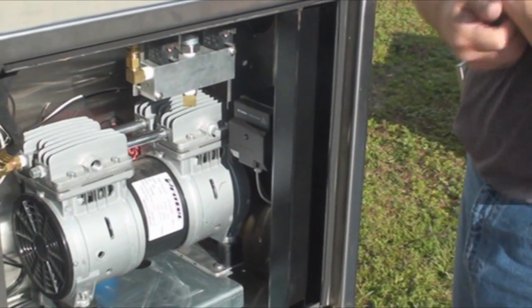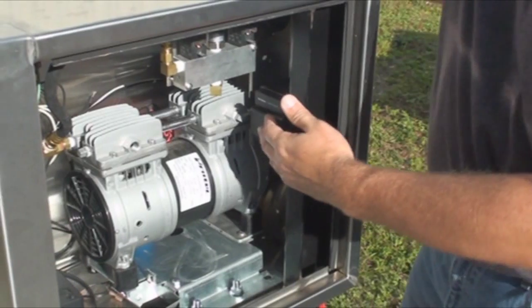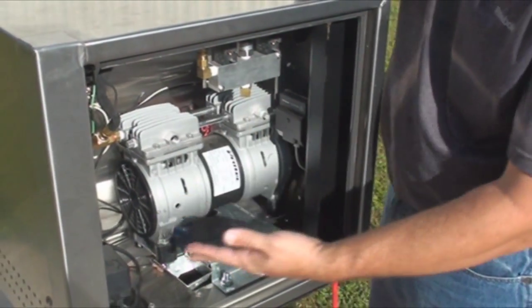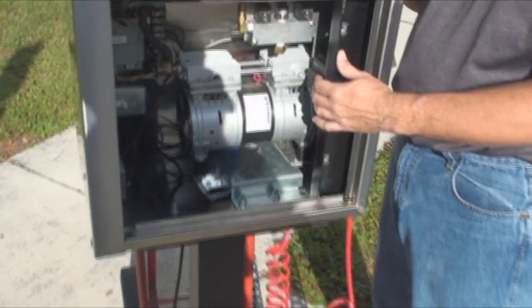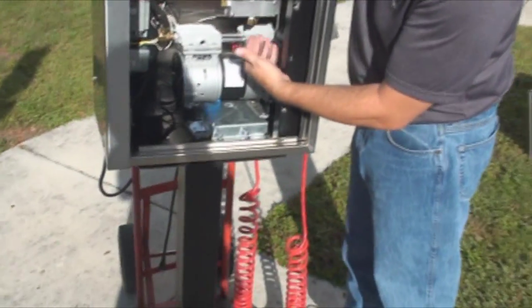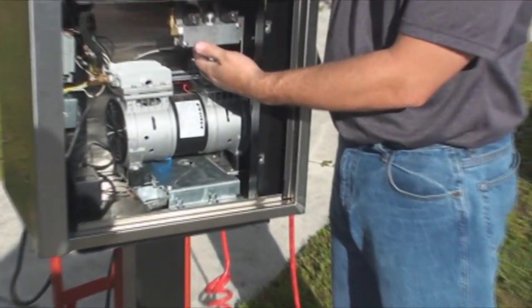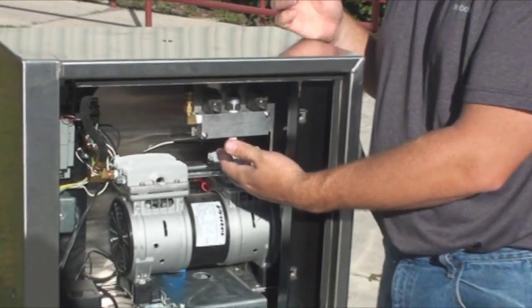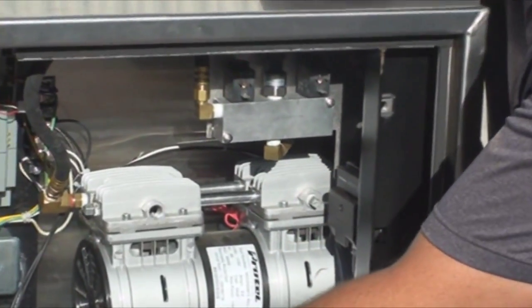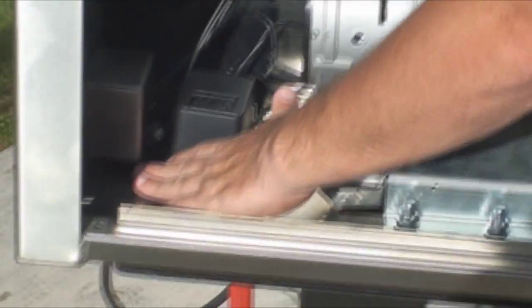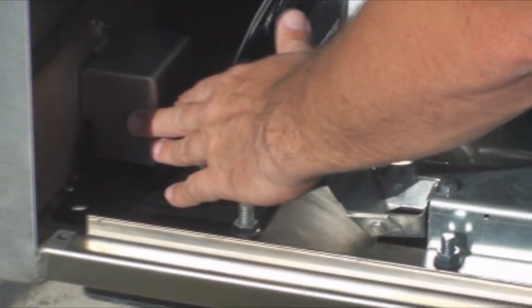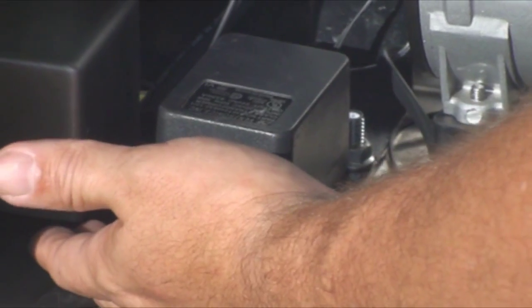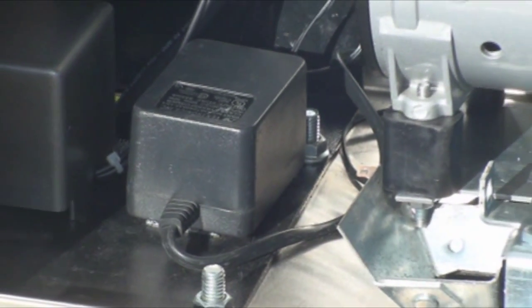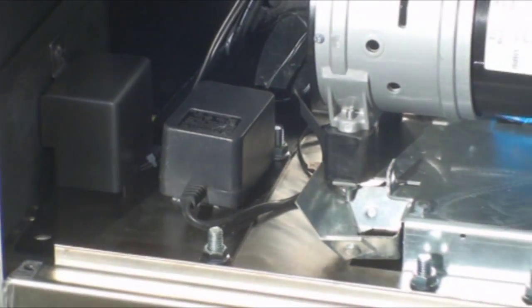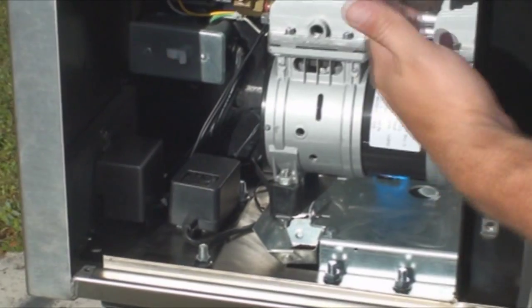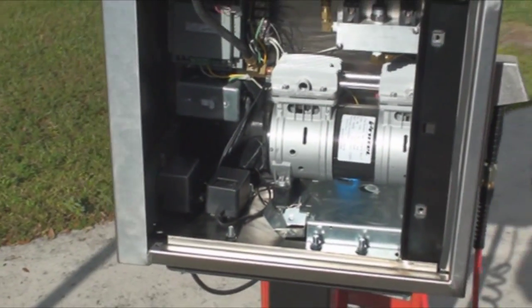ambient air temperature. The rest of the heater goes to heat the inside of the cabinet and keeps it about 40 degrees. And it also blows up on the manifold, and that's the reason we put it here, to keep the manifold warm. In the lower left-hand corner is the thermostat. And with the thermostat preset, you don't have to worry about winterizing, because in the warmer months, the heater won't turn on until you go into the winter months and the temperature drops.